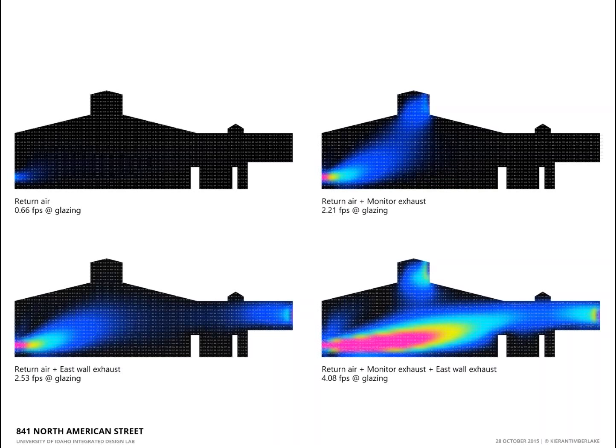So now we had started to move from understanding and using thermal performance data derived from sensors, just to understand, say, thermal diffusion and things like that, but also understand potential implications as far as renovations for our building. Now, this is a $100,000 decision right now. You don't want to make a wrong one. You're putting giant holes in your envelope. So by combining thermal data generated by the sensors in association with modeling, we're able to really validate some of those decisions.